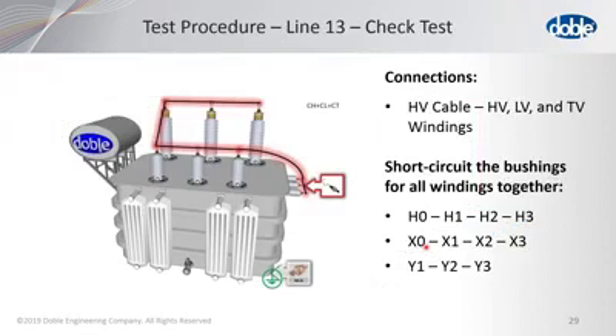Now, the test procedure for line 13 is what we call the check test. Of course, you've already got jumpers here, here, and here, but what we want you to do is include additional jumpers here and here. And that makes it so every bushing is going to be energized at the same time, and we'll measure all of the insulations to ground. The insulation of CH, CL, and CT will be measured.